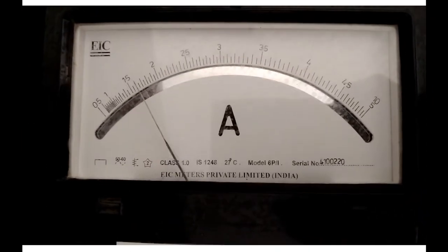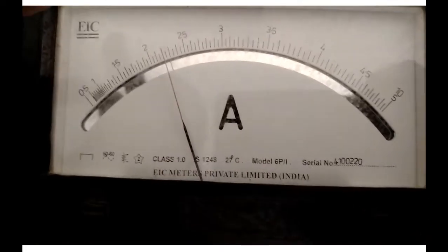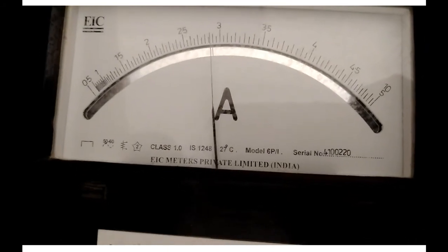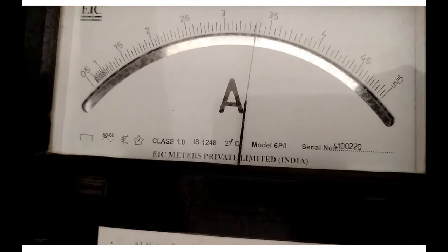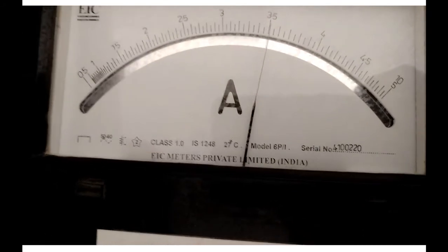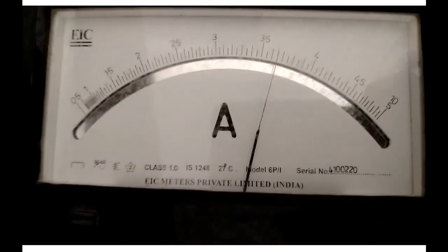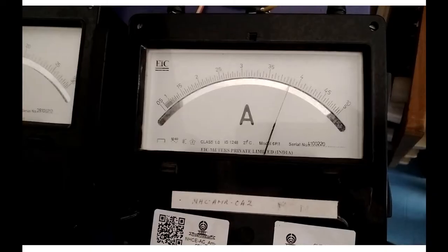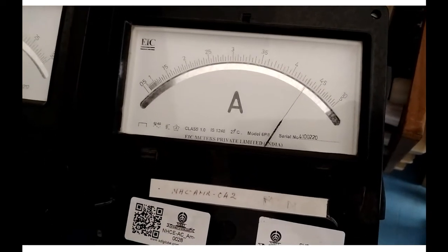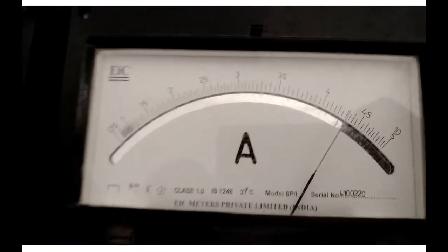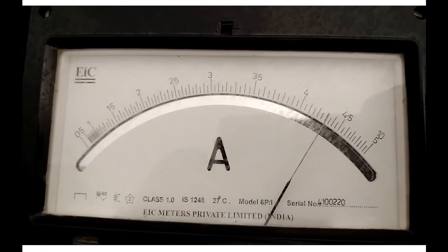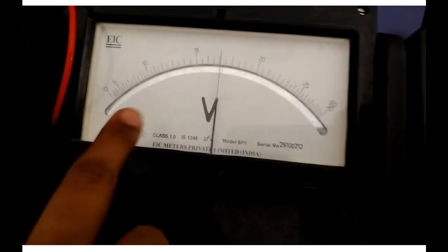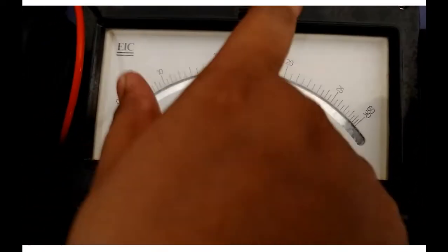You can see here the ammeter is connected to the 10 range, so whatever reading we get here we have to multiply by 2. I will keep it at 4.3. I am adjusting. Right, so 4.3 into 2 is 8.6. I have adjusted to the rated short circuit current. Now you have to measure this reading and the voltmeter reading. I have connected to the 60 range, so the short circuit voltage is the reading into 2. It is 17 into 2, right?